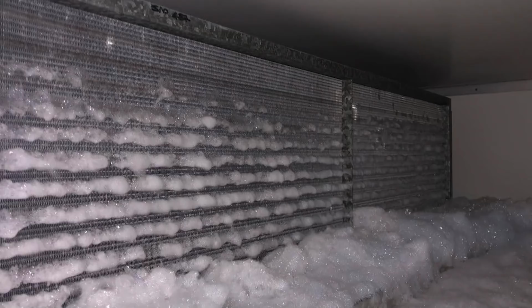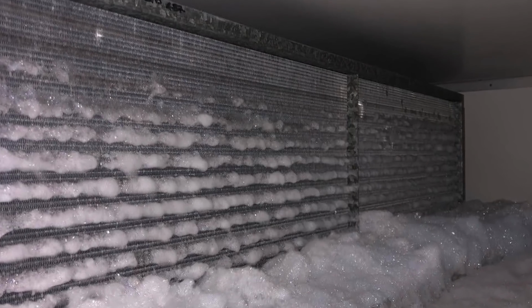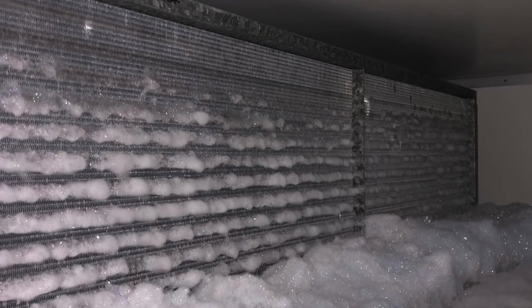So when they pressure wash, you're only getting about 5% of it, and it looks shiny—it looks great. You can go into air handlers in a hospital and they look like you could eat off of them. But when we go in and clean them, all of a sudden you see the foam just doesn't go through. There are these massive blockages inside them.